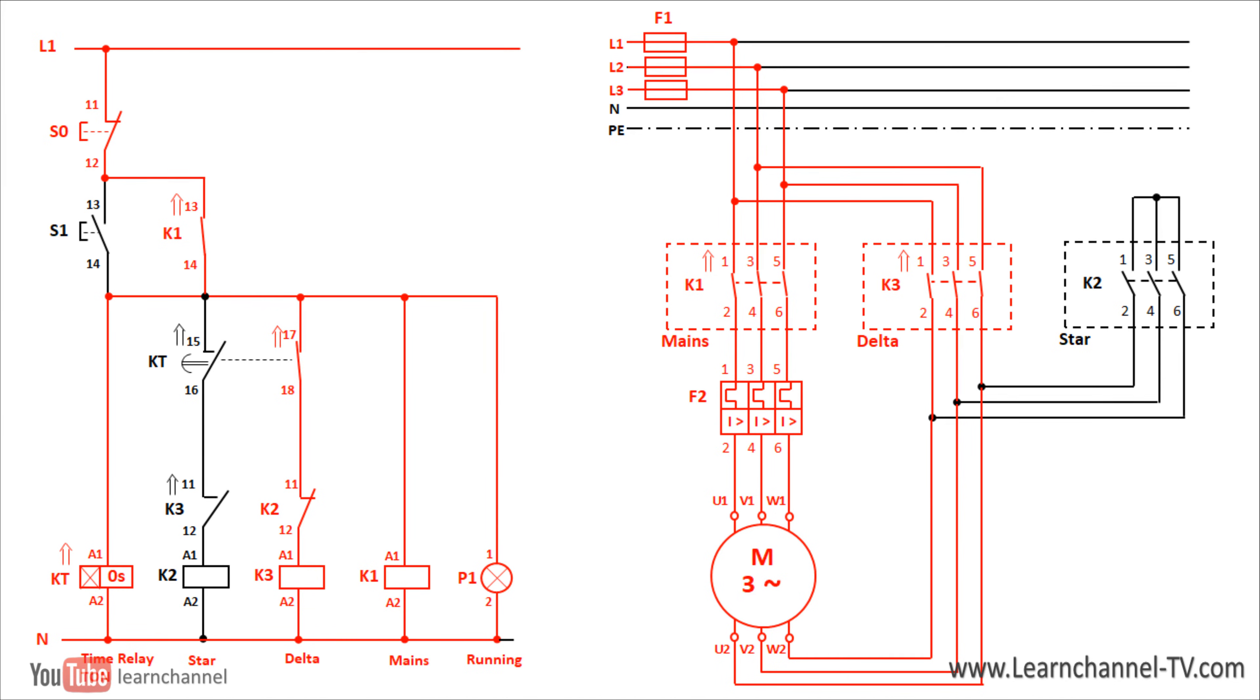At the same time, the on-delay time relay is energized. As soon as a certain time, which can be set at the time relay, has elapsed, the time relay switches. Thus, the star contactor is de-energized and the delta contactor is switched. Small remark: a normally closed contact opens faster than a normally open contact closes.